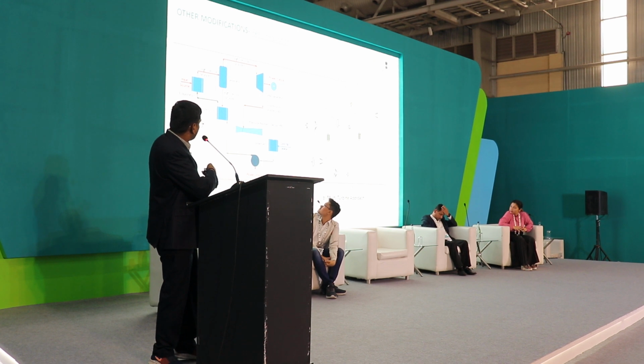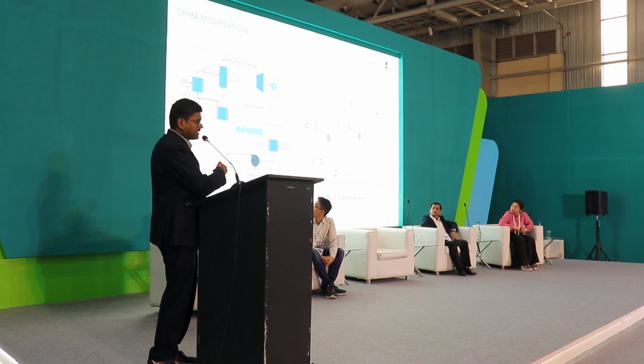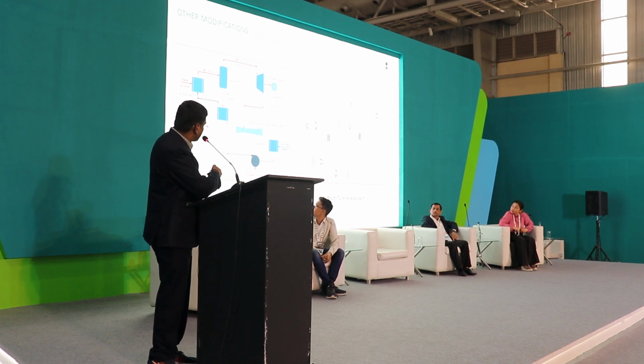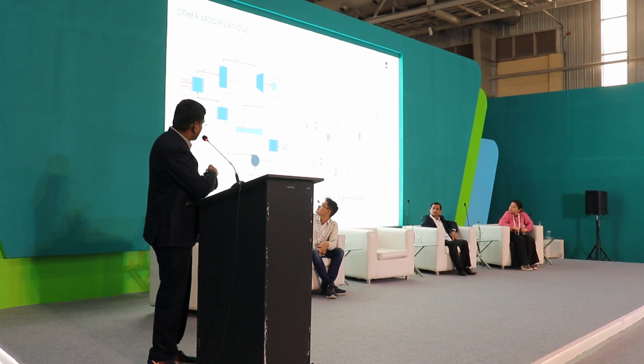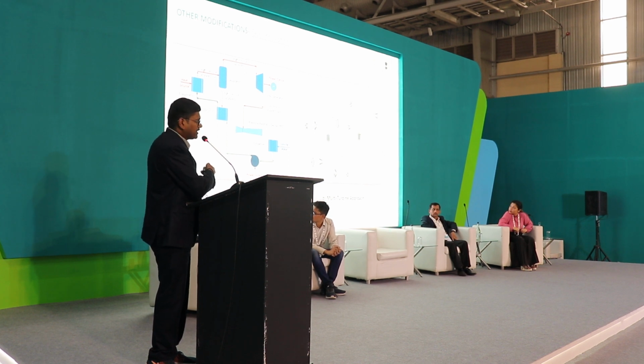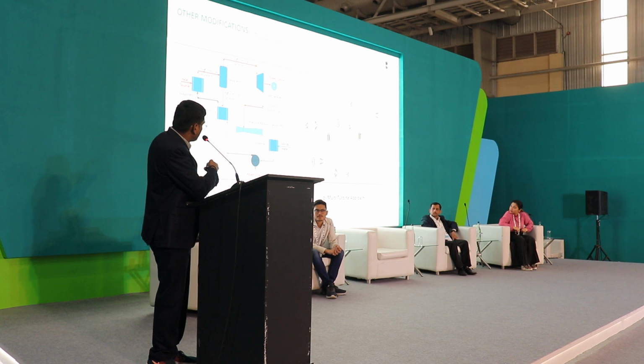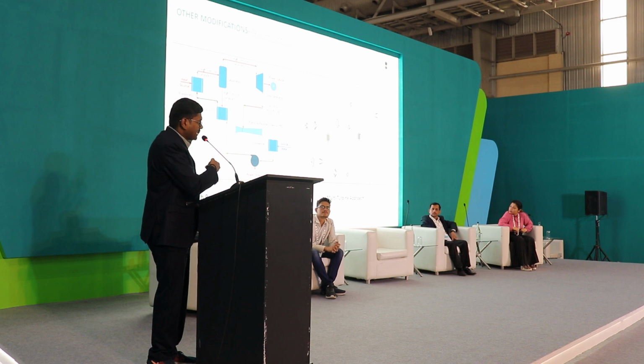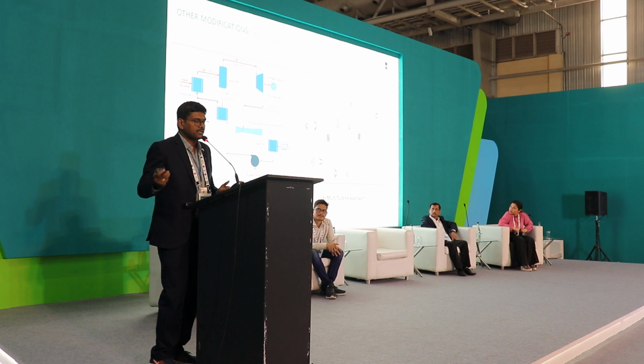The liquid from the recuperator is again at high pressure, but it has to be let down to meet the low pressure saturated vapor. One technique we developed - a pressure recovery device, though there is a Chinese patent on it, but we have tested it - uses the energy in the liquid side to take out the low pressure saturated vapor, so that on the exhaust of the turbine we can reduce the pressure further, improving the efficiency.